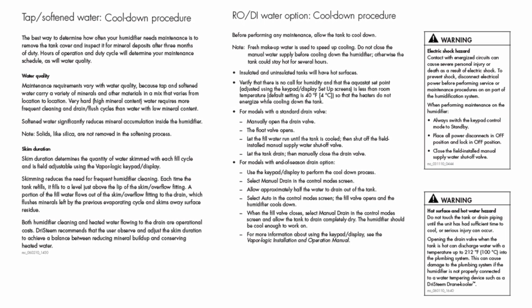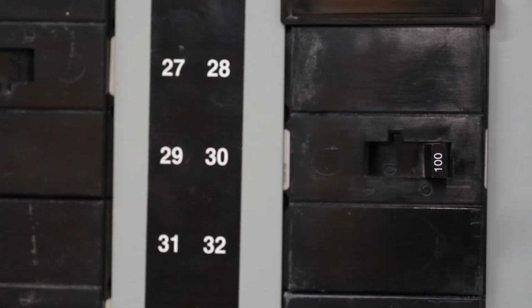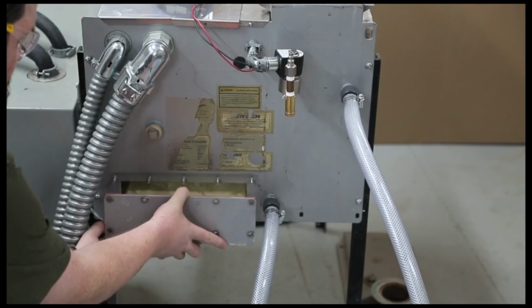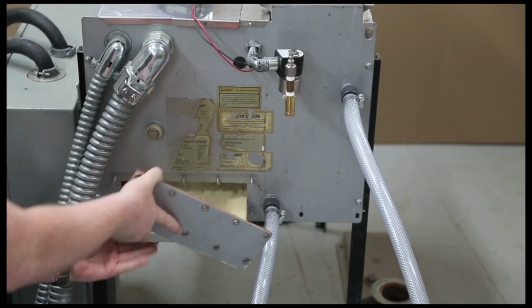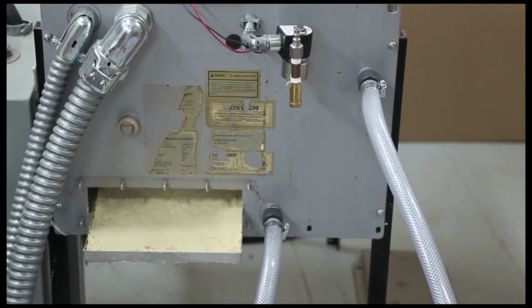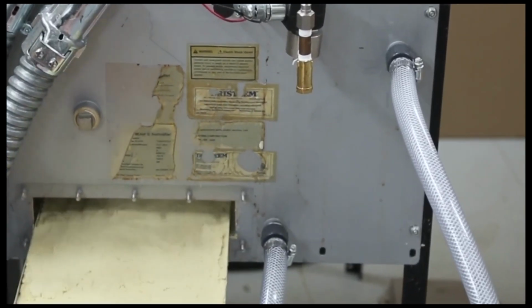Seasonally, or as required depending on water quality, cool down the tank and follow shutdown procedures in the IOM and disconnect power. Remove the cleanout plate. Slide the cleanout tray out and dispose of any loose scale that has collected in the tray. Remove any additional scale that has accumulated on the bottom of the humidifier tank. This should be done before the scale buildup reaches the heaters.